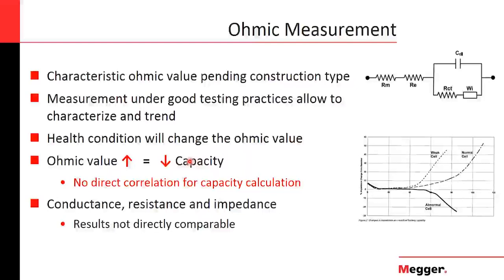Okay, so ohmic measurement. Every type of battery, every type of construction, we just mentioned the VLA, the VRLA, the NiCad batteries, will have a characteristic ohmic value. A battery is nothing else than an electric equipment, and any electrical equipment you can model with a network of resistances, capacitances, or inductances. And in this case, there's one model for the battery.